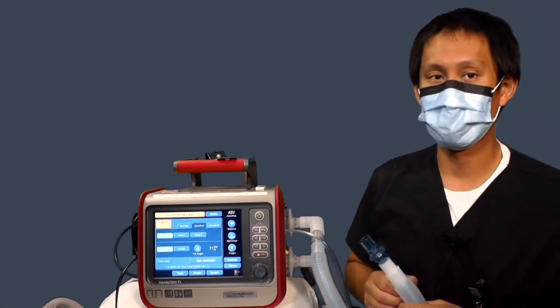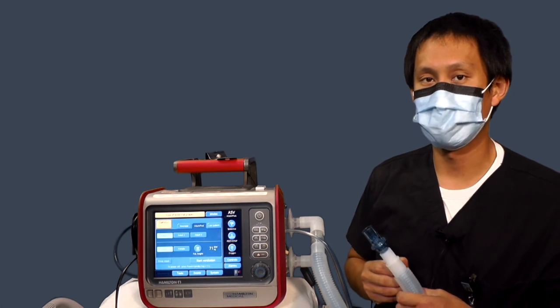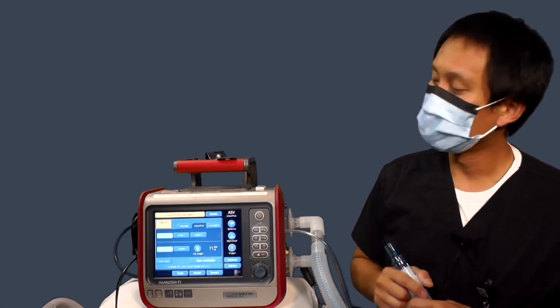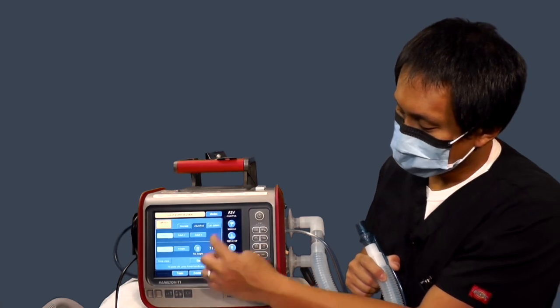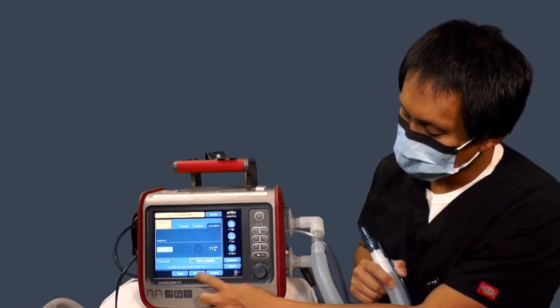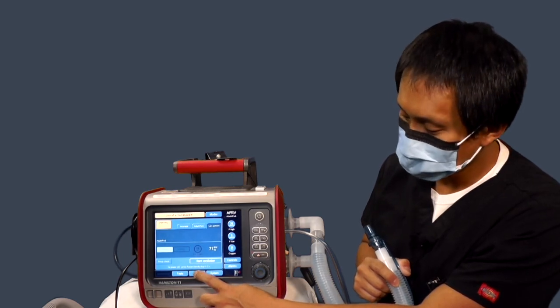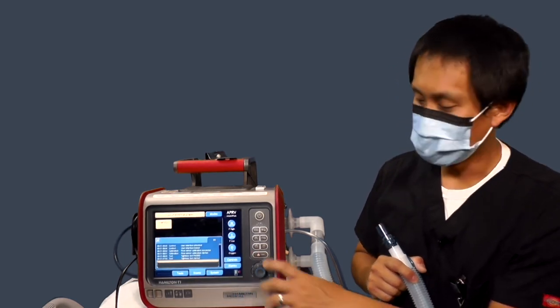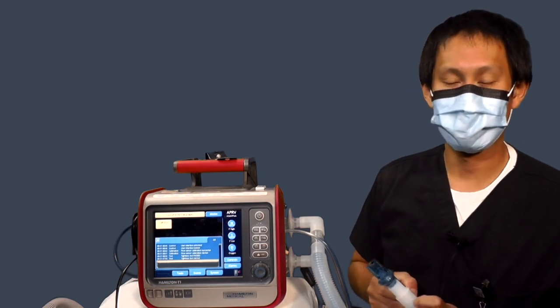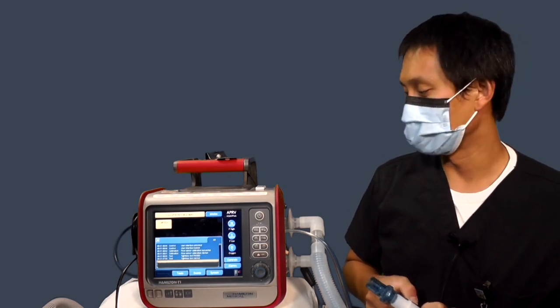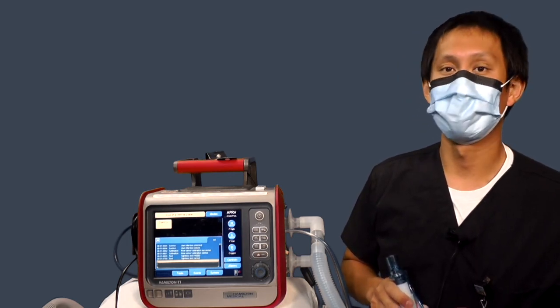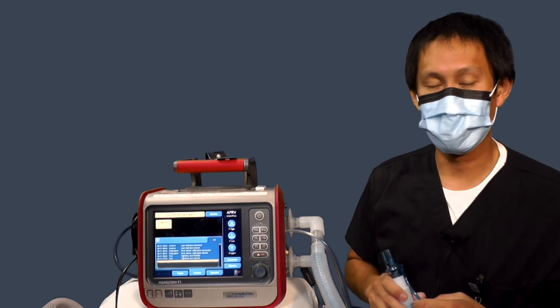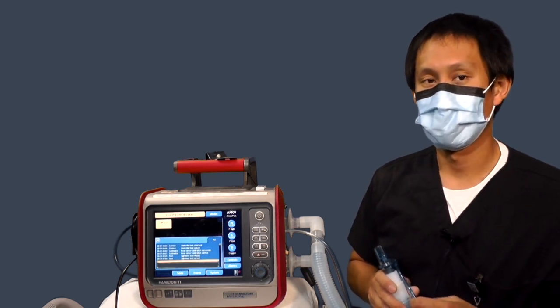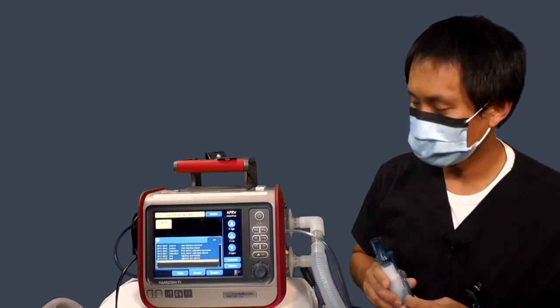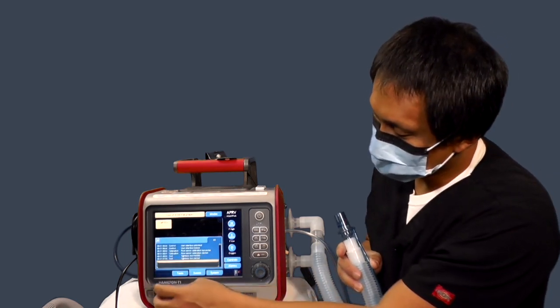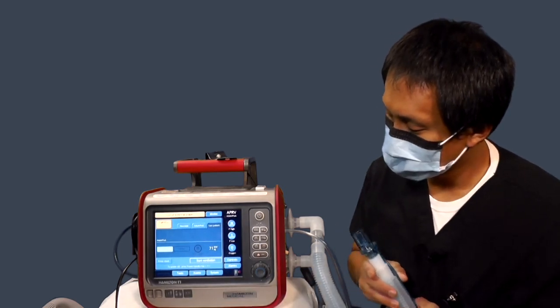This ventilator also allows you to go back and see the events from your last patient. To do that, you can hit the last patient button, you can hit the events tab down at the bottom, and it'll pull up all the events that occurred with your last patient transport. This is a one-in, one-out system. So as soon as you start this ventilator on another patient, it'll start dumping the data from your previous patient. Hit the X button to exit out of that pop-up box.